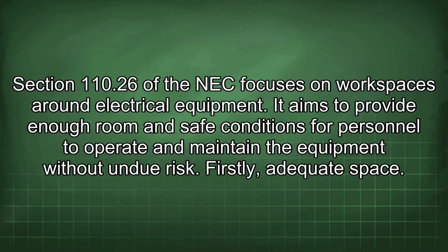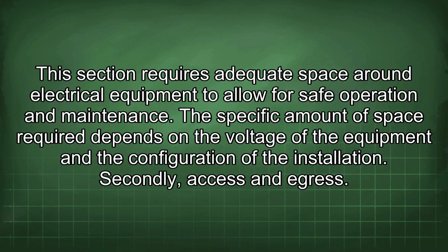110.26. Section 110.26 of the NEC focuses on workspaces around electrical equipment. It aims to provide enough room and safe conditions for personnel to operate and maintain the equipment without undue risk. Firstly, adequate space. This section requires adequate space around electrical equipment to allow for safe operation and maintenance. The specific amount of space required depends on the voltage of the equipment and the configuration of the installation.